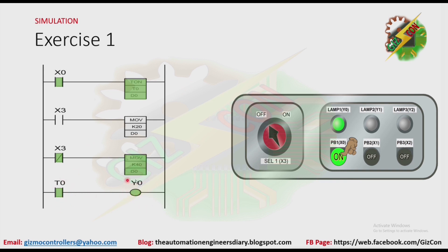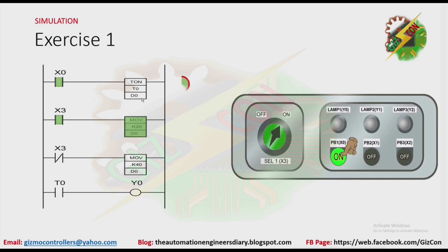That will cause the normally open contact of T0 here to turn on, and that will make Y0 to turn on. Now after turning on the selector switch, the value of D0 is now 20, which makes the timer preset value 2 seconds. Let's press PB1 — the timer is activated after 2 seconds and that will make Y0 to turn on.